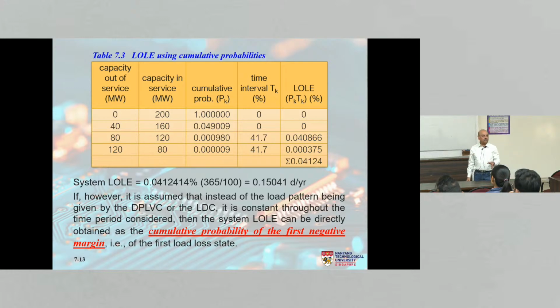That's the advantage of the cumulative probability capacity table, which I also mentioned yesterday. If you look at the cumulative probability table, assuming the load to be constant at 160 megawatt, when we have 40 megawatt out, we are still okay, correct? When we have 40 megawatt out, we are still okay, no loss of load. When we have 80 megawatt or more out, then the cumulative probability is 0.000980, correct?